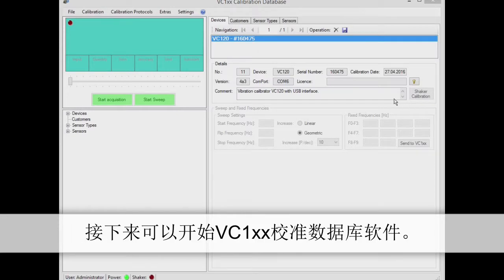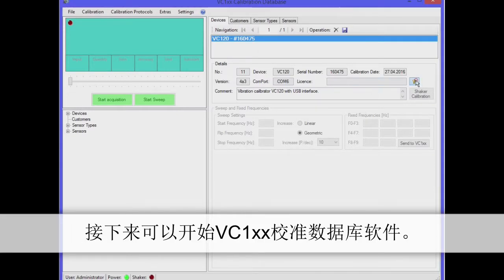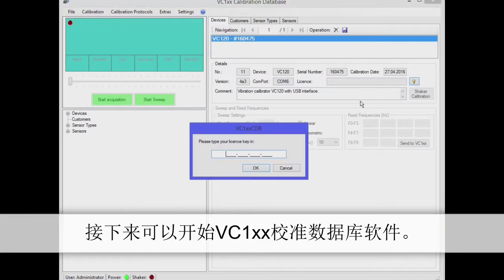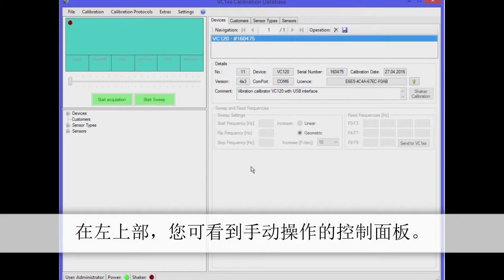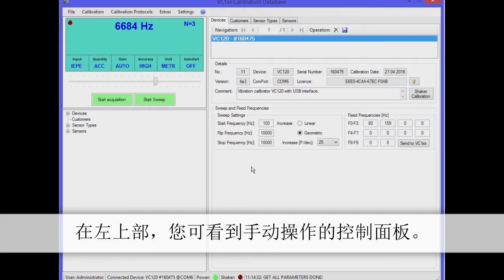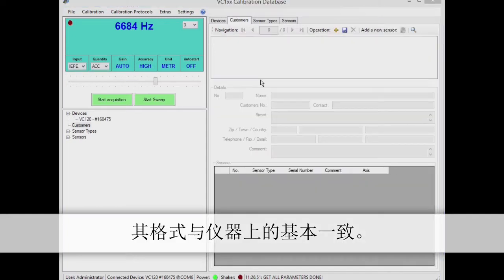Now start the calibration database software. The instrument will appear on the display with its serial number. When using the software for the first time, you'll need to enter the license code, which you receive with your instrument. After entering the code, you'll have access to all program functions.